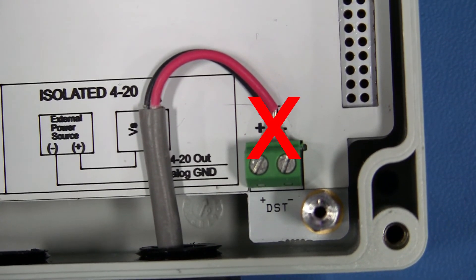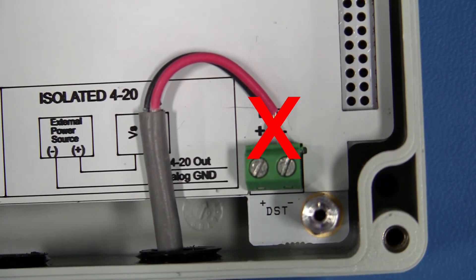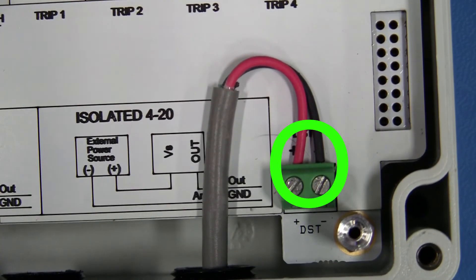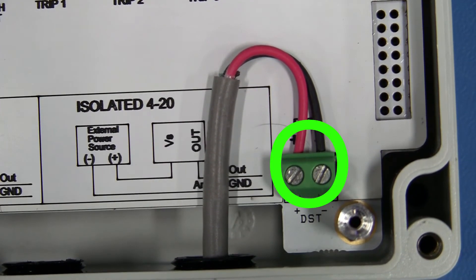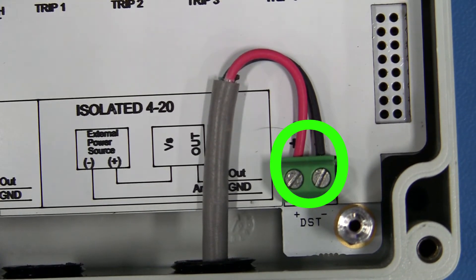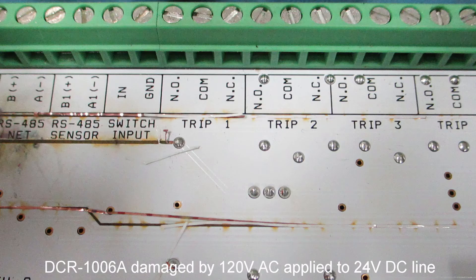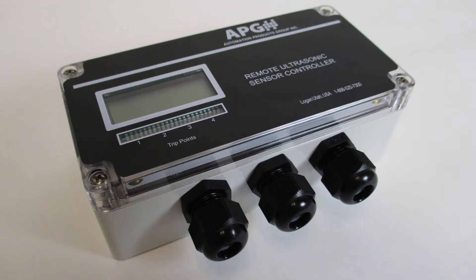Use caution when installing wires. Ensure all wire strands are twisted and properly installed in the connector. Strip wire ends so that the insulation covers the wires as close to the connector as possible without being pinched. To prevent damage, ensure your power supply is compatible and wiring of the DCR and all components is correct before applying power. See DCR-1006A instructional video number 1 for a guide to powering your DCR-1006A.